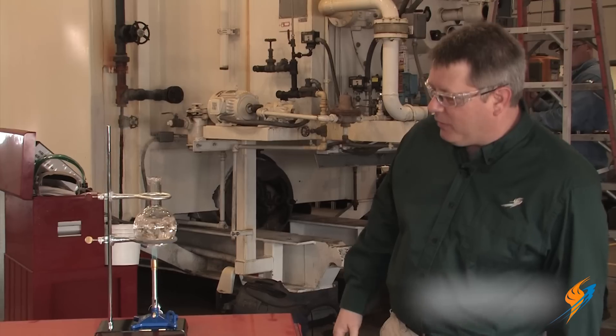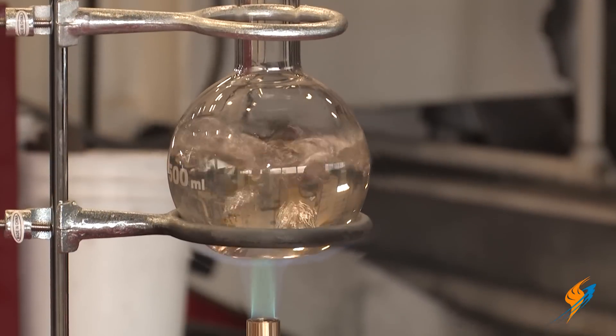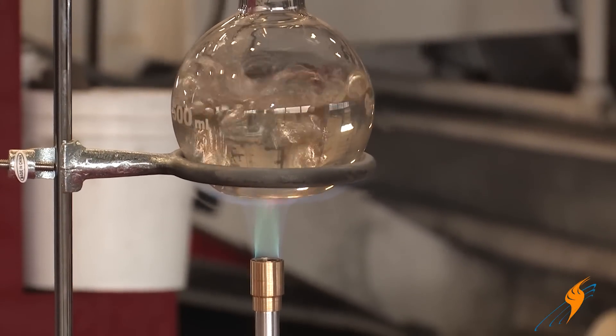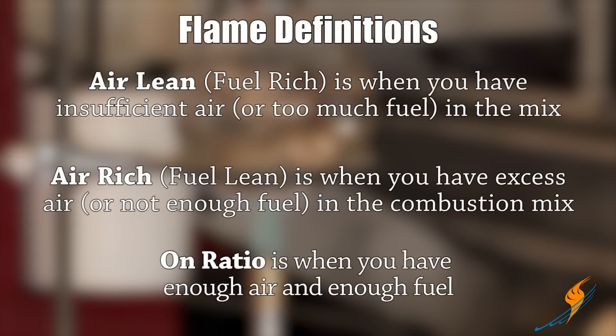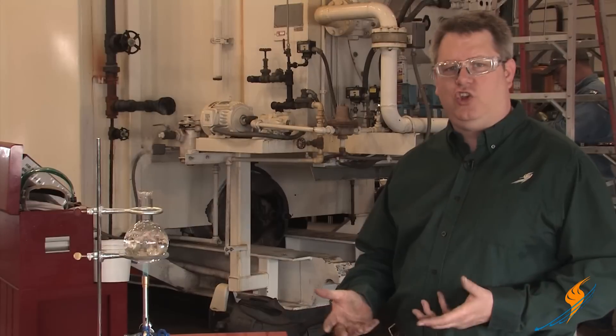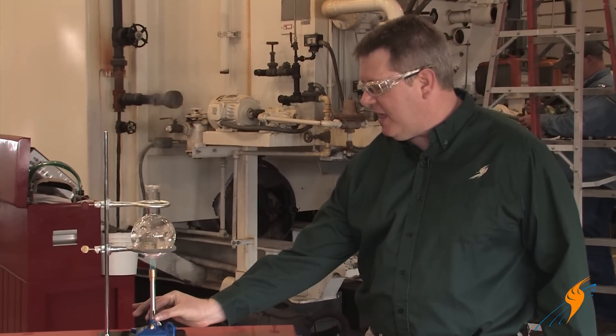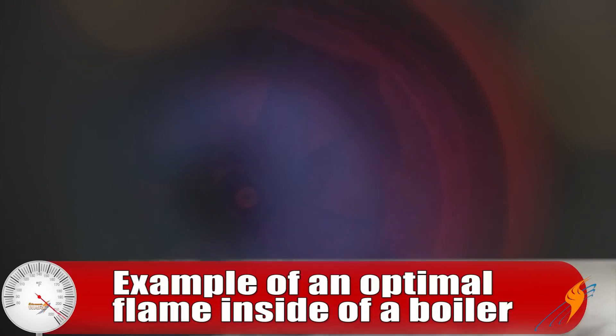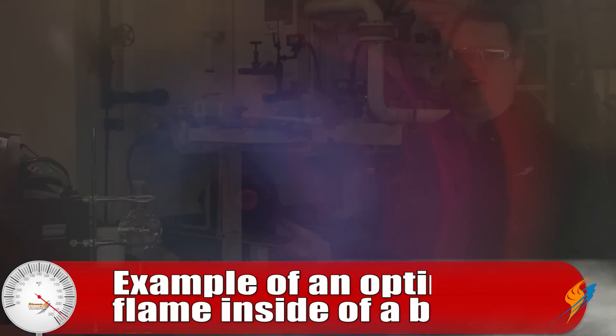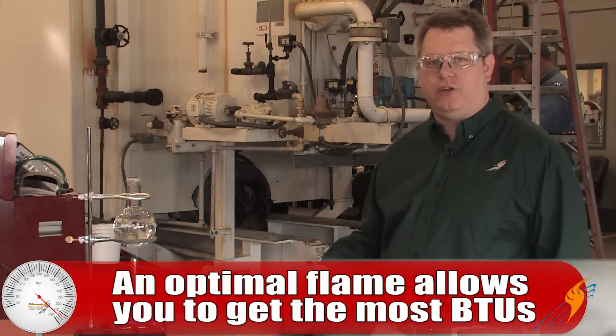What we've got an example of here is a very lean flame because the air aperture on this burner is wide open. What we do when we tune a boiler is use feedback from the stack to adjust that and get the optimal flame. An optimal flame allows you to get the most BTUs out of your cubic foot of gas.